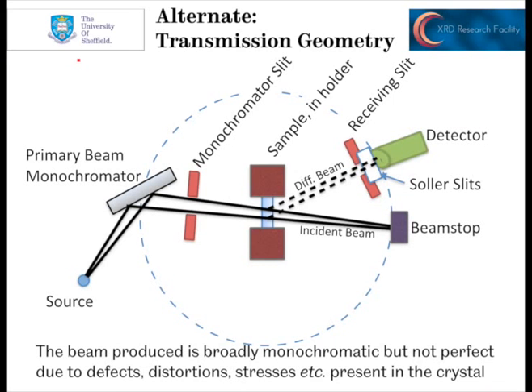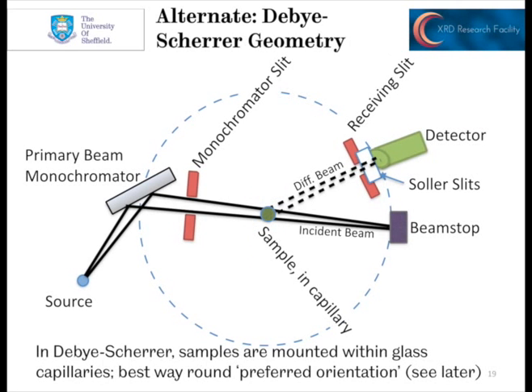We can also see a sample shown here in transmission mode, as it would be on our Stoe machines. After what we've talked about regarding absorption of X-rays, the sample thickness is going to be really crucial — if the sample is too thick, the beam won't go through and you won't see anything in the detector. We also have the option of the Debye-Scherrer geometry. This is where the sample is a powder — and it must be a powder — mounted inside a glass capillary. If you have preferred orientation in your sample, running in Debye-Scherrer geometry is the best way to address that. Hopefully this short video has given you a good idea of the different experimental setups available here in the XRD research facility, and some of the more common aberrations that can cause headaches in data analysis, along with advice on how to avoid them.